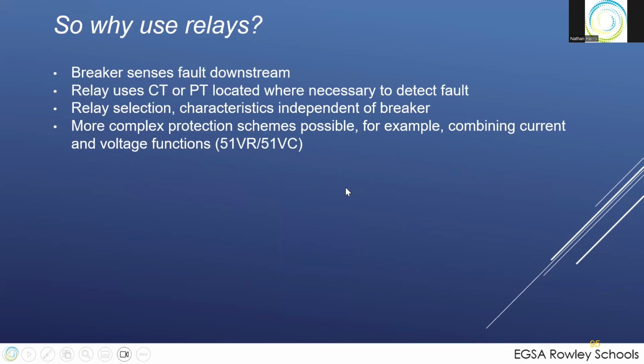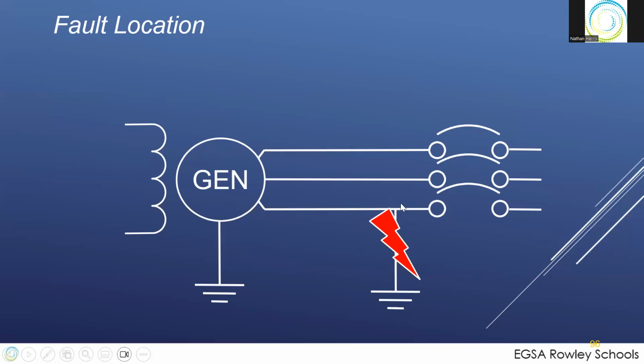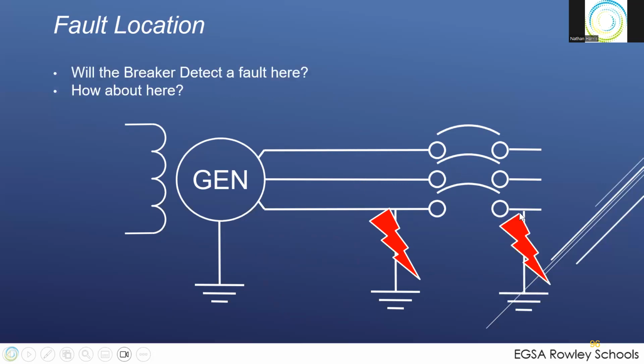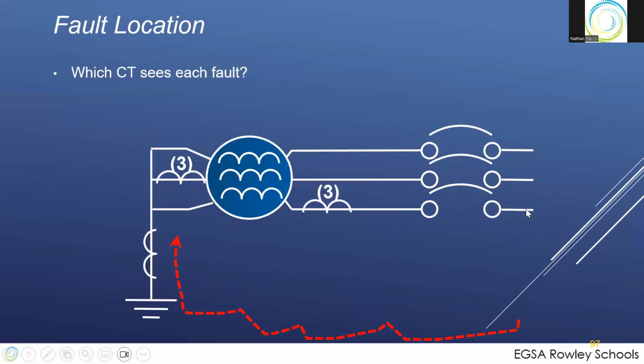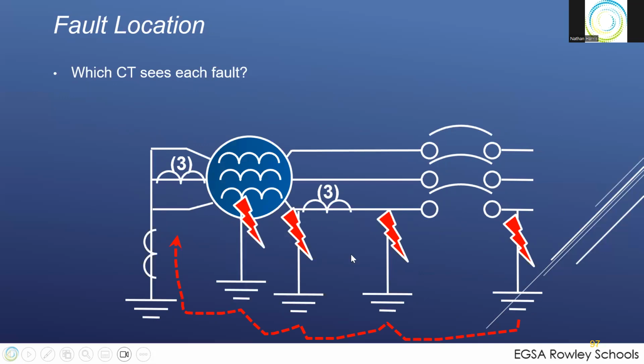We often also use relays, and this will talk some more about medium voltage here. Why do we use relays in different schemes and different types of protection? For example, if we have a fault here, right, will this breaker detect this fault? Obviously not, right? The second location, it will, right? So if you have a fault between the generator and the breaker, it won't be detected. Here it will be. So we won't trip, we'll sit and burn the generator up. But if we use a CT, the CT can detect the faults here, or here, or here, or even here. Any of these locations, a CT here on the neutral leg will find that, or a set of CTs in the phase will find that.